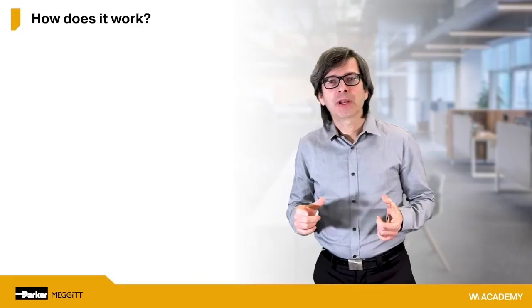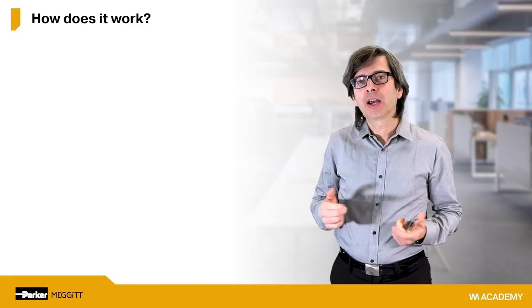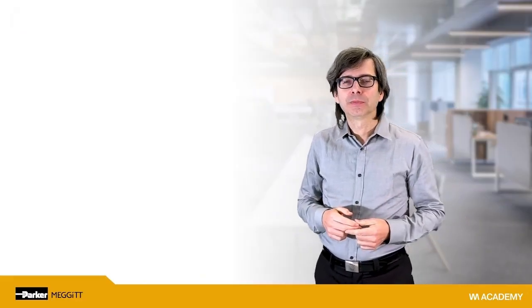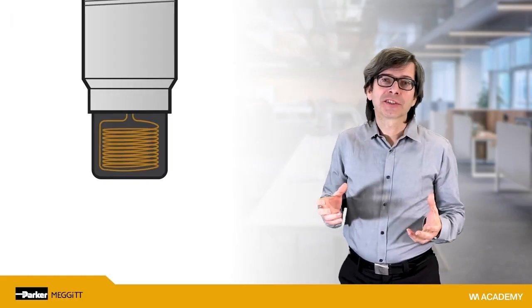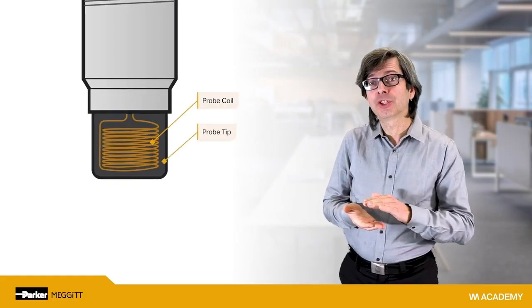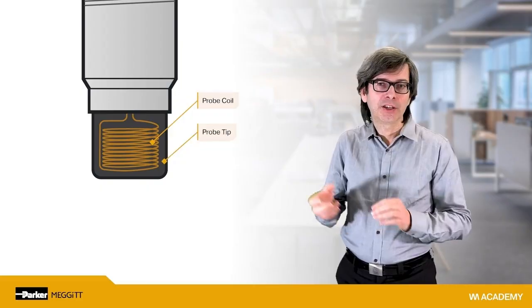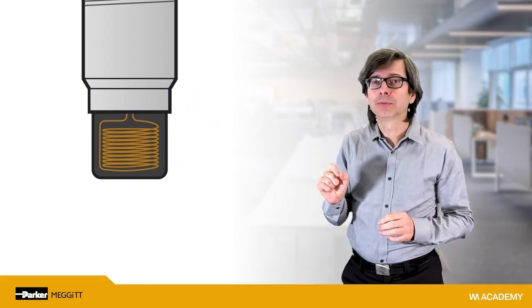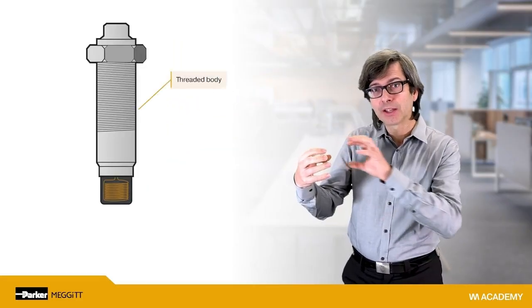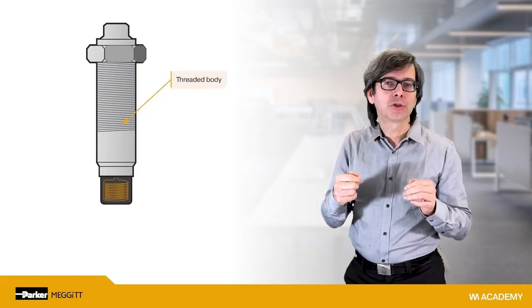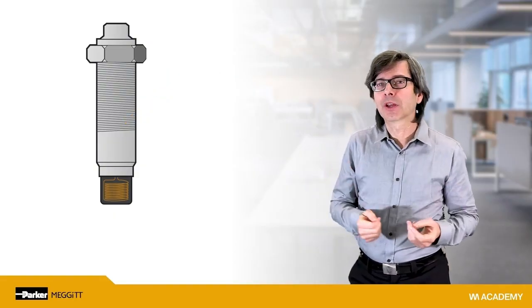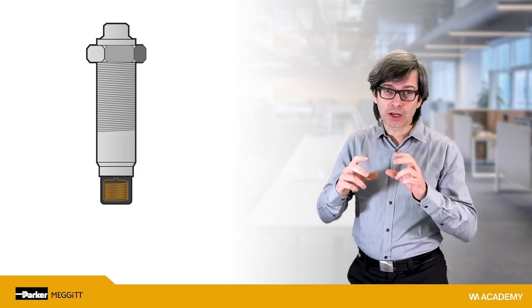Now I'm going to explain the basic working principle behind eddy current proximity probes. The probe consists of a coil which is shaped like a flat disc, and it's inside the tip of the probe. The tip is attached to the metallic body, which is usually threaded, so it can be attached to some kind of bracket or support using a couple of nuts.